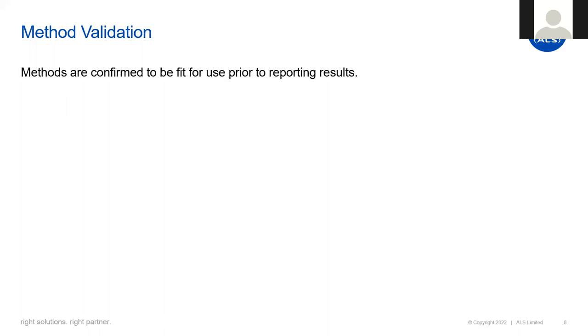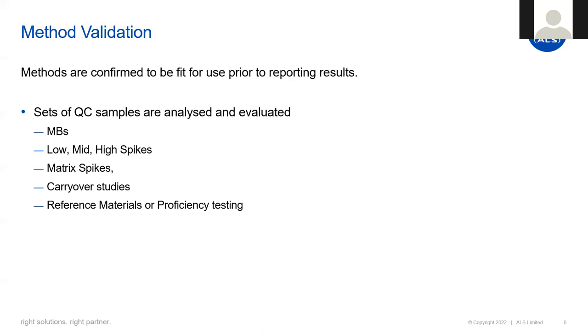Another use for QC is validating our methods. Method validation is a huge topic, but in general terms it is the process of how labs show that they're able to perform methods properly — and also the point where appropriate QC types are chosen. To show control over the method, labs analyze different sets of QC samples, including sets of method blanks, laboratory control samples spiked at different concentrations, matrix spikes to ensure expected matrices don't have negative effects, instrument carryover evaluations, and reference materials or proficiency testing samples. All of these are evaluated against validation objectives established at the beginning of the process to establish fitness for use for a method.